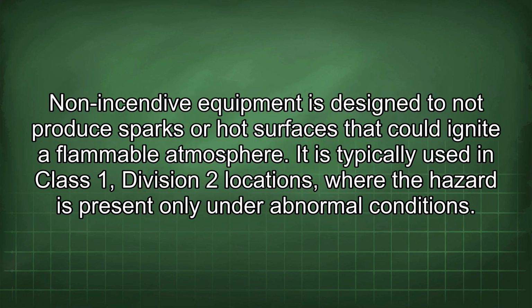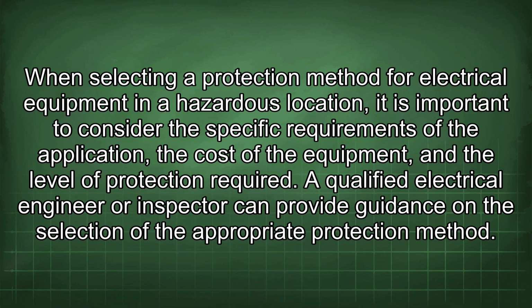Non-incendive equipment is designed to not produce sparks or hot surfaces that could ignite a flammable atmosphere. It is typically used in Class 1, Division 2 locations where the hazard is present only under abnormal conditions. When selecting a protection method for electrical equipment in a hazardous location, it is important to consider the specific requirements of the application, the cost of the equipment, and the level of protection required. A qualified electrical engineer or inspector can provide guidance on the selection of the appropriate protection method.